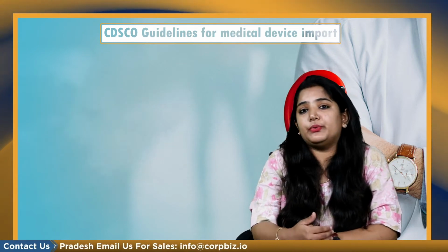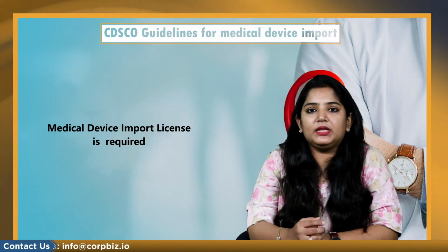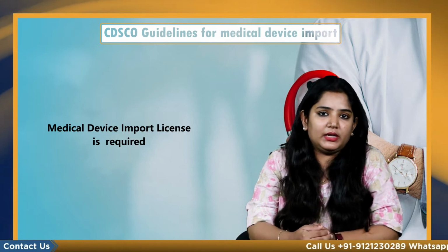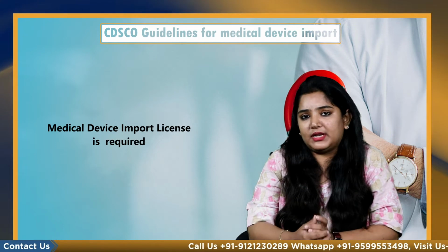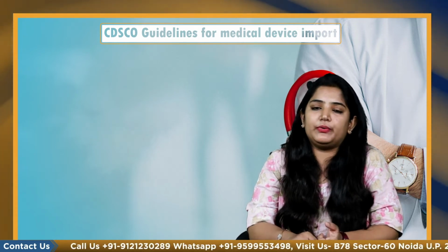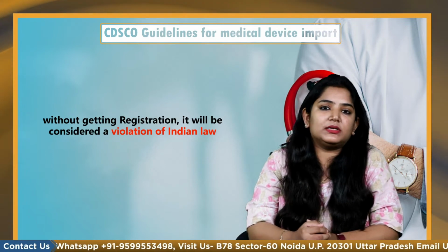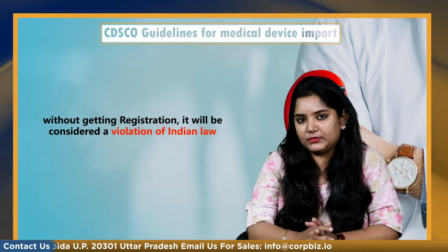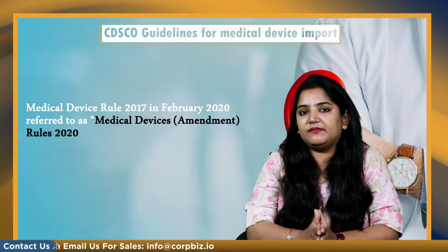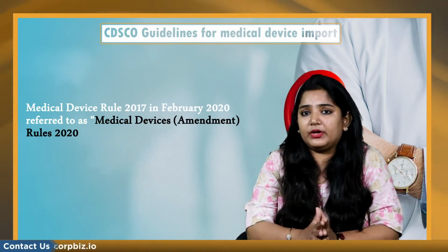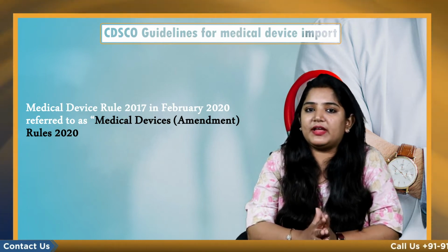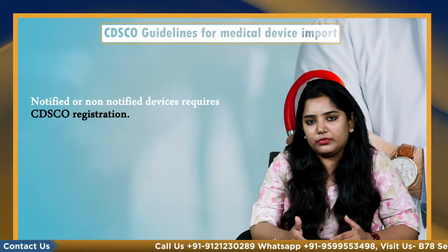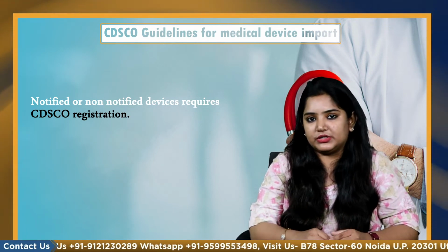Medical devices entering the Indian market must be in compliance with the guidelines set forth by the CDSCO. All medical devices imported into India are required to have a medical device import license. If any medical device is imported into India without registration, it will be considered a violation of Indian law and thereby invite a penalty. There was an amendment in the Medical Device Rules in February 2020, referred to as the Medical Device Rules Amendment 2020. Now all devices, whether notified or non-notified, require CDSCO registration.